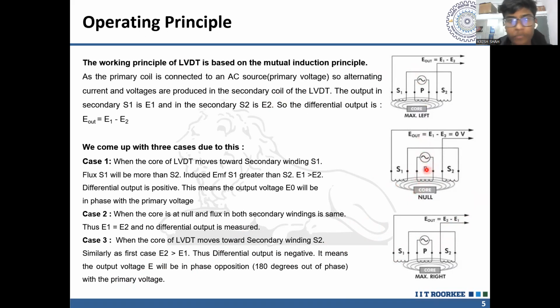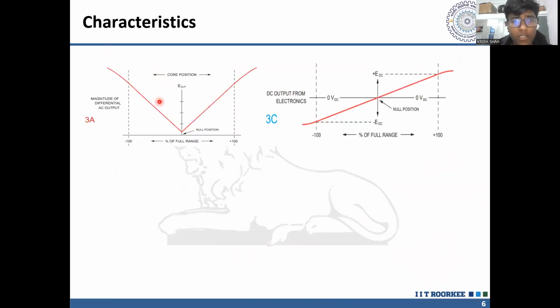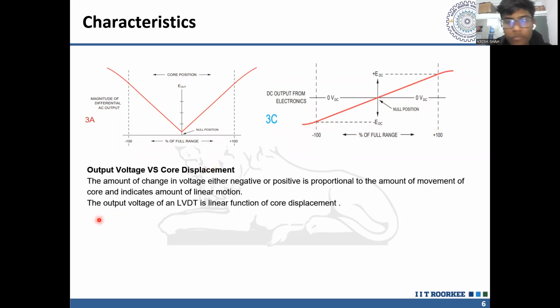Now, what are the characteristics? As we said, the voltage goes to zero, and when the core goes to the S2 side, the voltage increases again to the same magnitude. This is the characteristic curve, which shows the movement of the LVDT core against the output measurement. When we plot this, we get a linear range from here to here, and after some range the linearity decreases and it becomes non-linear. Output versus core displacement is the characteristic.